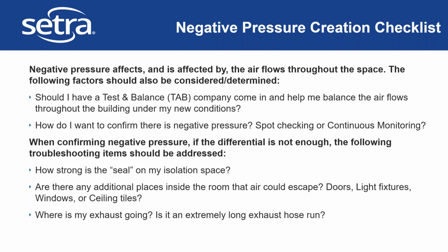There's a balance between completely sealing off every nook and cranny in a room versus having tons of gaps in walls and windows and ceiling tiles and doors that are going to impact the ability of a portable unit to pull negative pressure. So those are a couple of areas to think through if you were to have to go down the path of troubleshooting the creation of negative pressure.